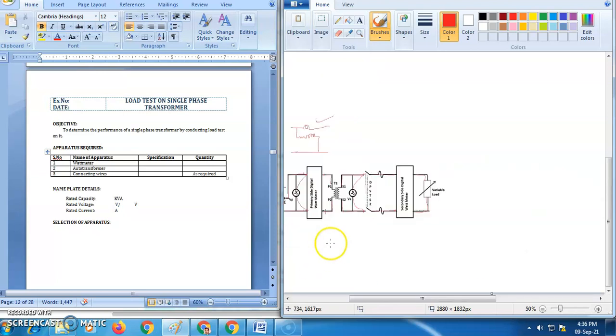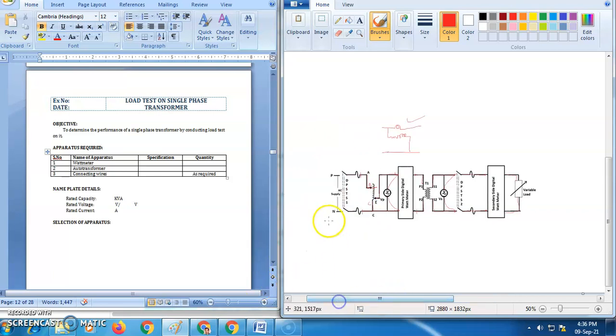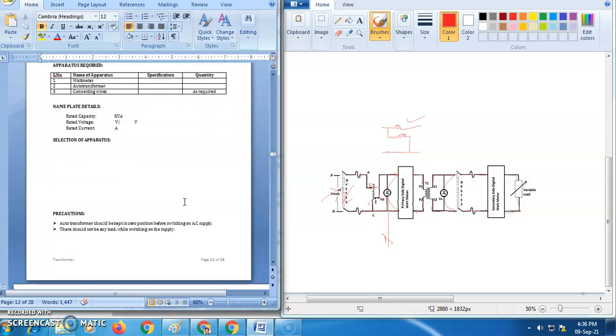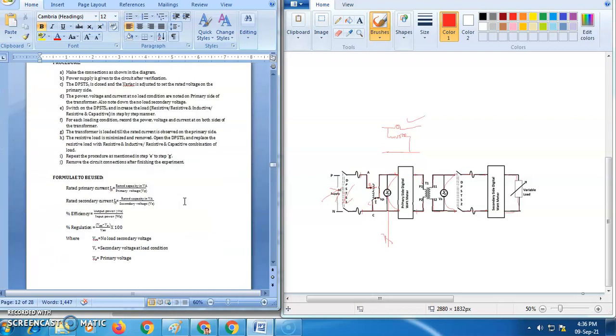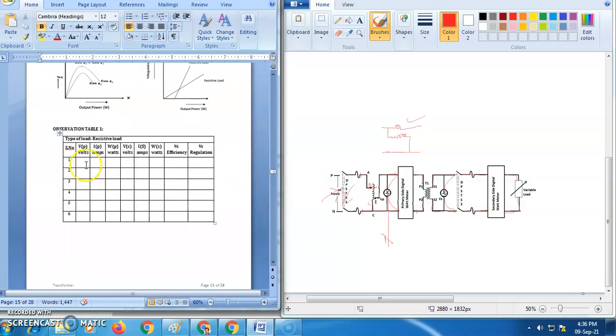So now the procedure is, you need to give the supply to the circuit diagram, close the DPST switch 1, and adjust the variac such that the primary side reads rated voltage, right? So at this condition, you need to record a first set of no load readings: primary voltage, primary current, primary input power, secondary voltage, and secondary current, which obviously will be 0 when this DPST is in the open condition, and power is also 0. So this is the first reading.